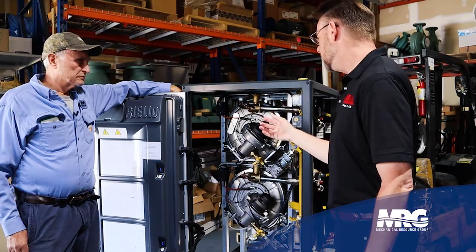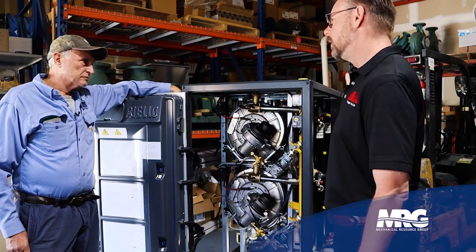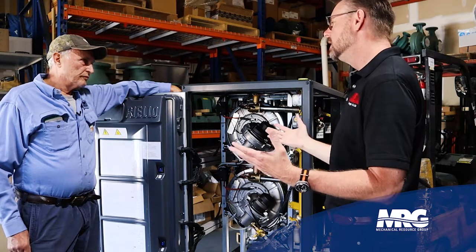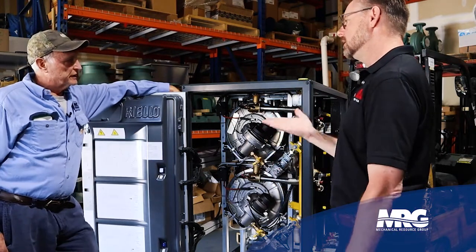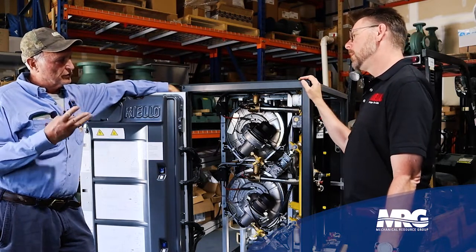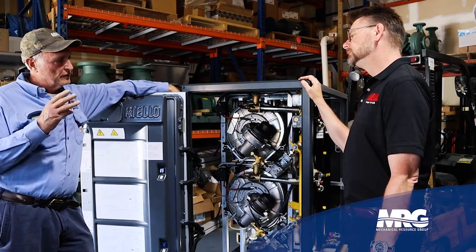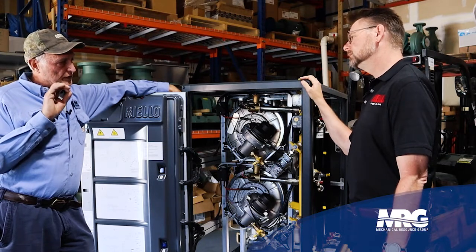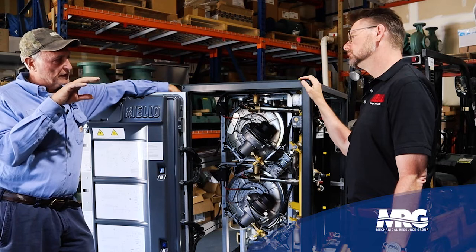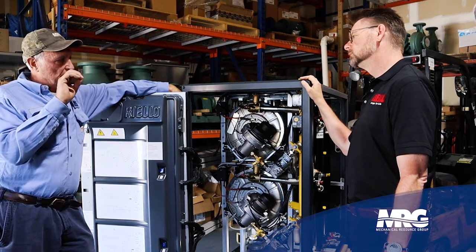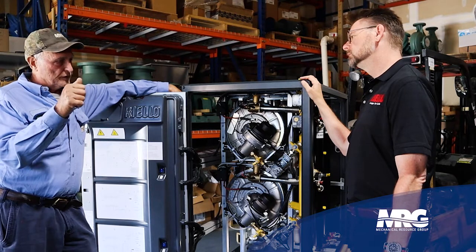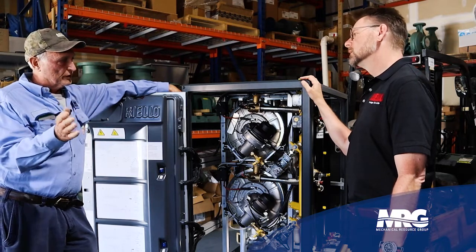Now, was that unit down for lack of circulation? Were either of those situations with the low water cutoff or the circulation, was that a crisis? Was it a thing that they could let go? No, it had to be taken care of immediately. And the whole thing is if you trip the relief valve, and I've seen 3 models from other vendors do this, they'll collect air in the collection circuit, depending on how the boiler's piped. And the sensor will trip low water. You walk up to the relief valve, you just pop the relief valve, let the air out, and away you go.